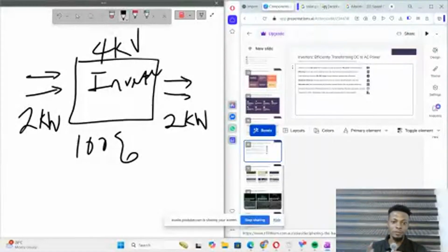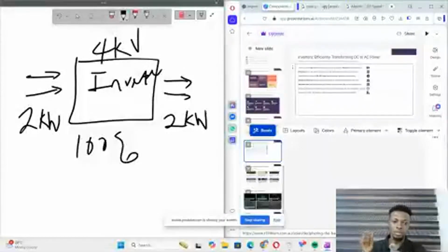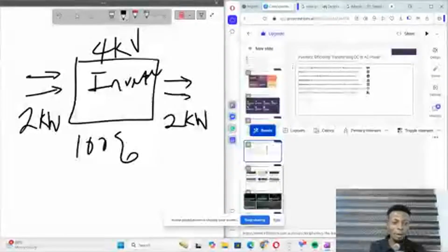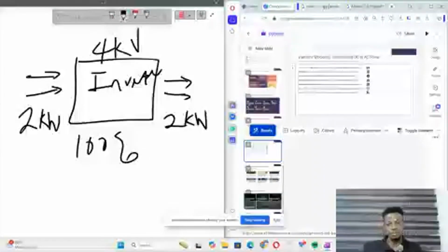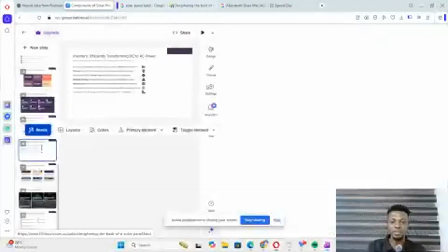Your inverter is mostly inductive, because of the function of the inductors or transformers inside it, which makes it more of an inductive load. An inductive load has reactive power, and that reactive power is counter power, which means you won't get the full power supplied to the inverter at the output. We'll talk about that later in the course. Just understand for now that the inverter cannot be 100% efficient.